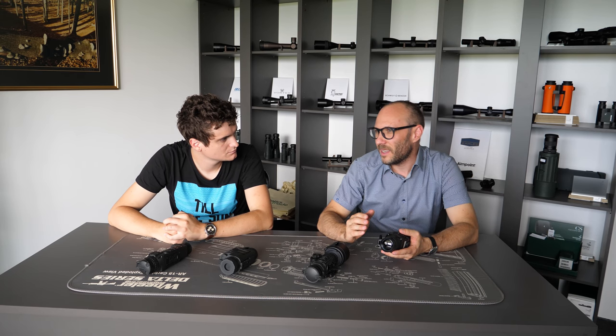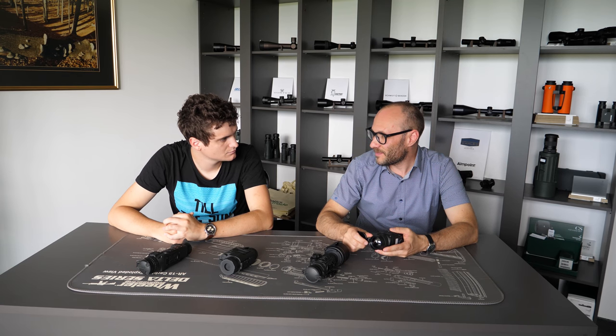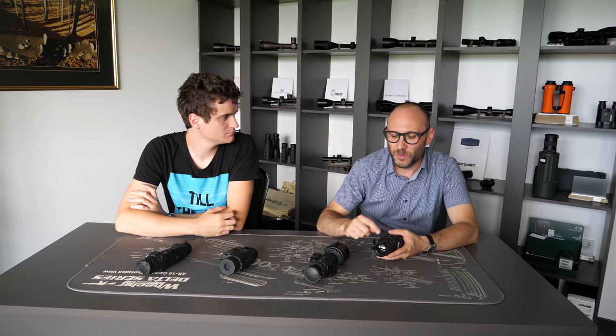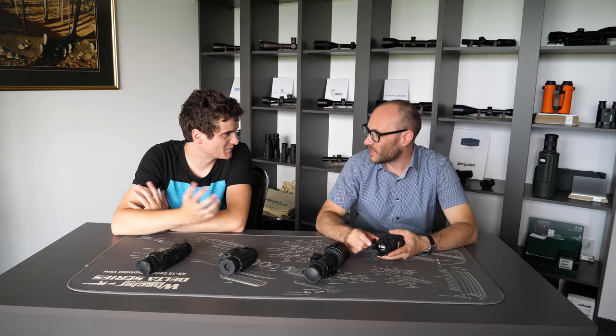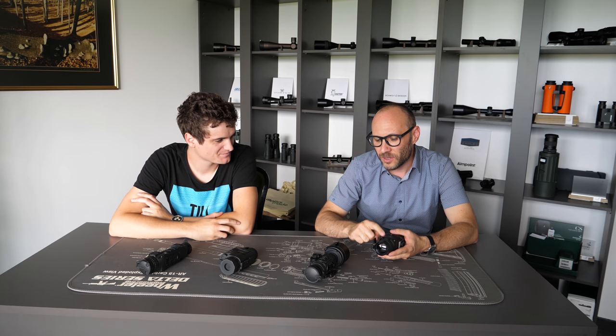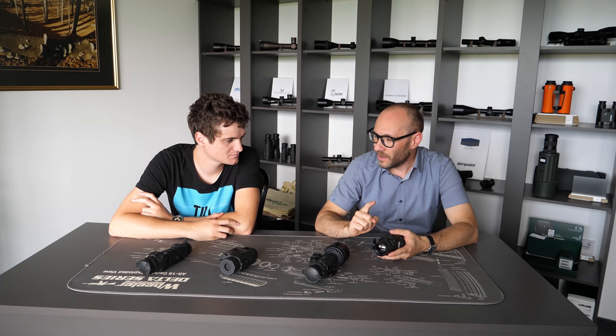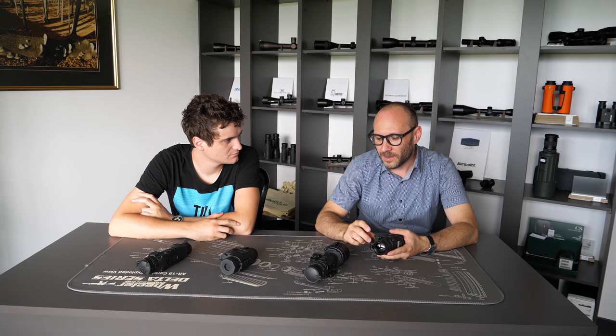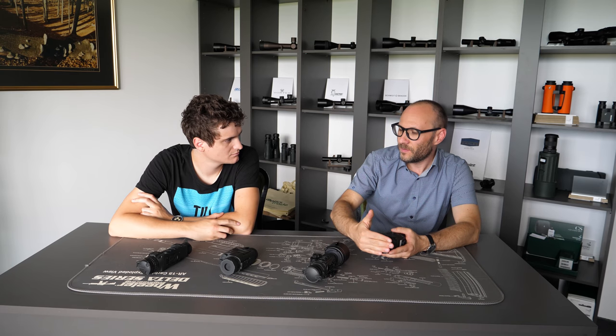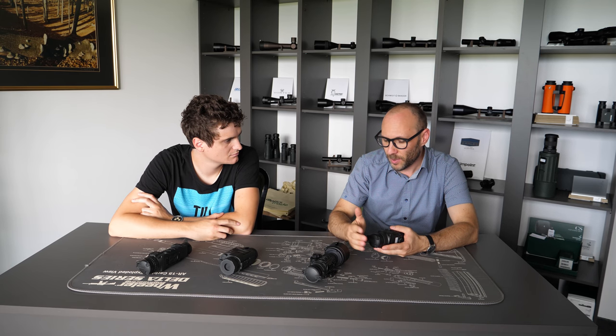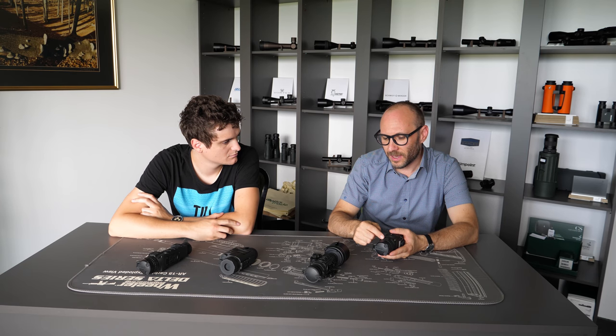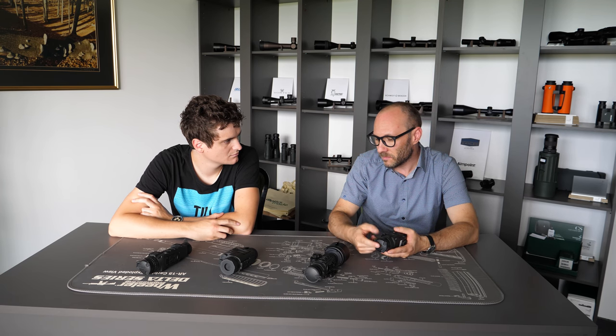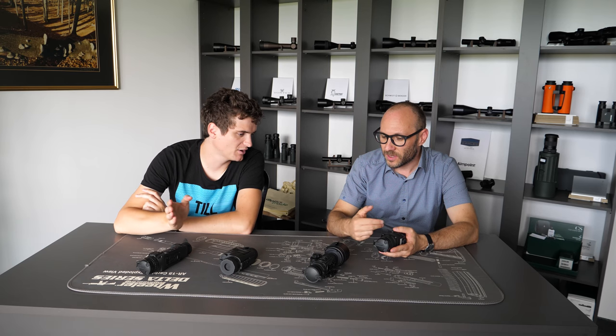Even though semi-automatic and manual are misleading terms, because in both cases you push the button and start. They're both manual calibrations, yeah. But the difference is that because the shutter release produces sound, they added the manual option, which doesn't use the shutter. It relies on you closing the front lid, the front cap, and then pushing the calibration button. The shutter doesn't close, but it recalibrates the sensor because the device knows that you closed the cap. So you can do that much more silently, probably.